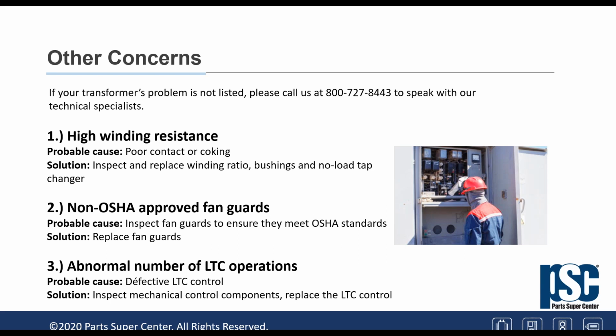Abnormal operation of the LTC. What operates the LTC is what we call the line drop compensator. What this does is sense the load, and the operator says, if this load or this voltage changes more than 10, 15 volts in so long, and we have a timer, then you change the tap. Now, if the tap changer operates too often, most likely the timing that we set is not good enough. But it could also be, as it's written here, an LTC control. These are things that could be investigated, like mechanical control components.